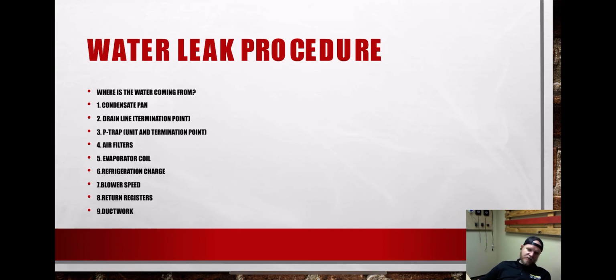So, water leak procedure. I'm recording this on August 31st, 2020. We have performed more water leak service calls this year than any other summer that I can remember by far. The humidity the last 2 weeks has been absolutely insane. So I'm probably 250 to 300 water leak service calls in the past month and a half or so, which is unusually high. We've had unusually high humidity, and when that happens, we get water leaks.